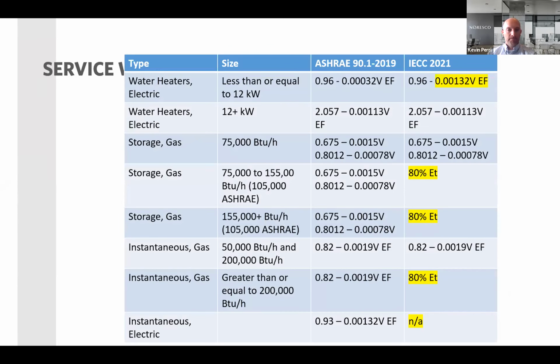So let's now look at the other thing in the differences category for service water heating. Again, try to make this as simple as possible. On the left side, we have our type of water heaters, our sizes, and then we have ASHRAE 90.1 in one column and IECC 2021 in the other. You can see there are a lot of similarities, but there are also some very minor differences. But again, just trying to make it easy for you to read. If you know what systems you typically see or use or design to, go ahead and find that in the table and see if there are any differences between ASHRAE and IECC. And that's it for the service water heating side.